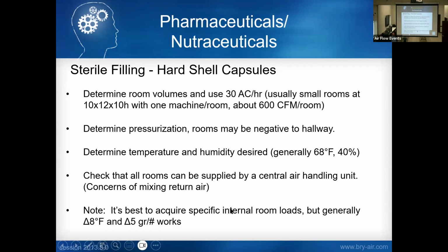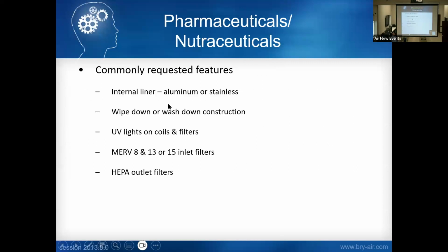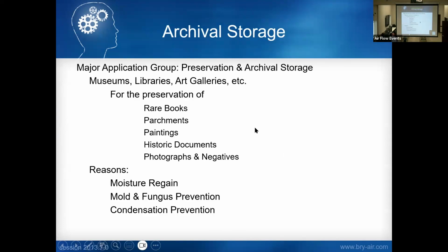Low conditions are somewhat hard to do on this, but typically we see about 8 degree F and about 5 grain delta. So if we want to control the room at, let's just say 35 grain, we need to deliver about 30 grain to that room. Again, same kind of requirements, wash down, UV lights, high filtration.